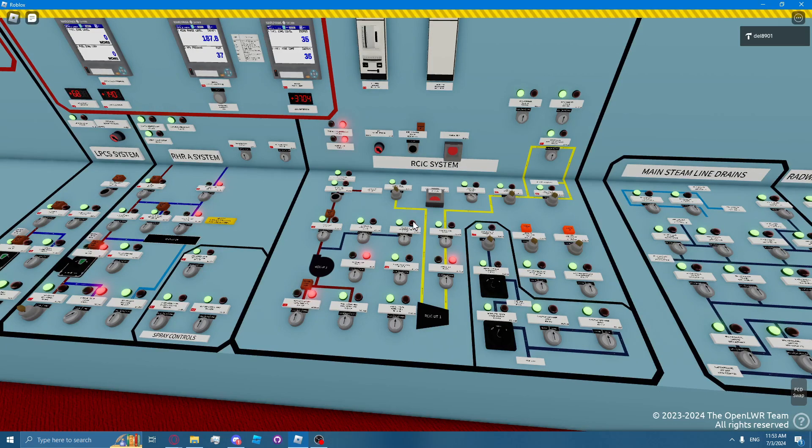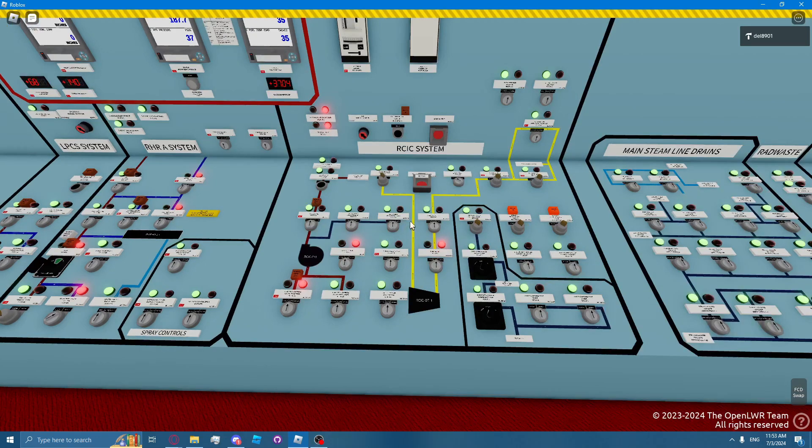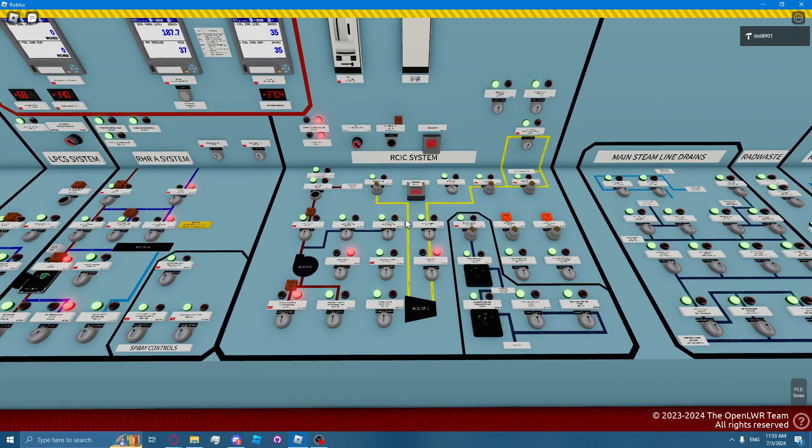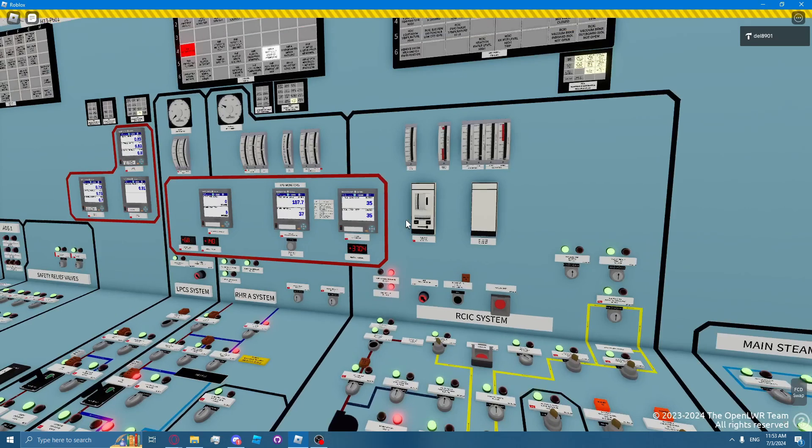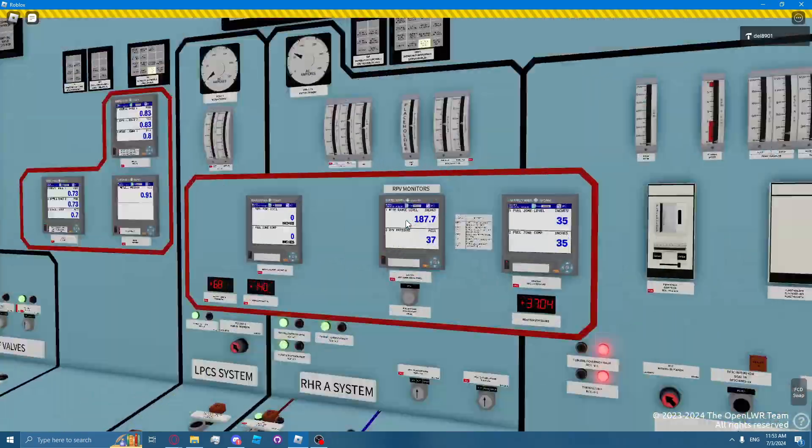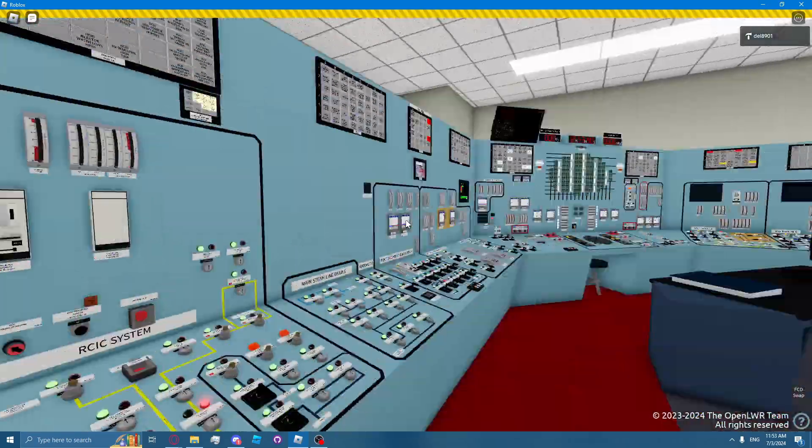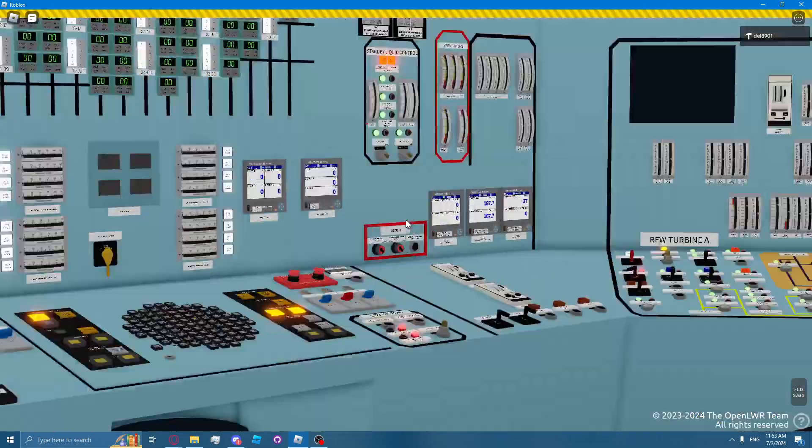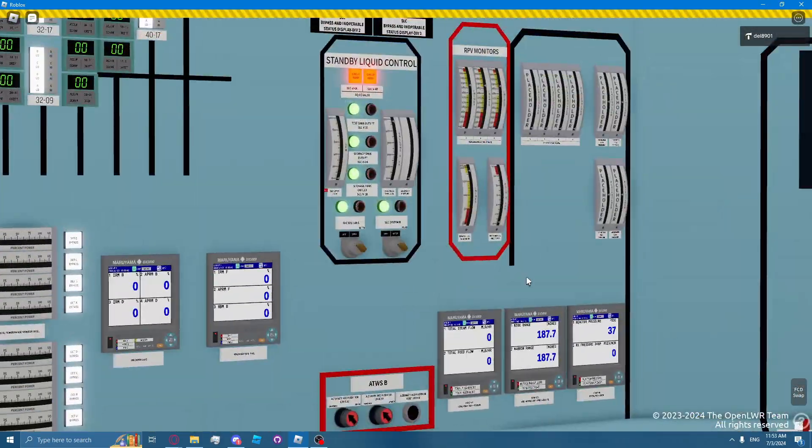The normal standby lineup for RCIC is having the condensate storage tanks on the RCIC suction. The RCIC system is automatically initiated at reactor level 2, which is plus 109 inches, which is indicated by wide range on either P601 or on P603.